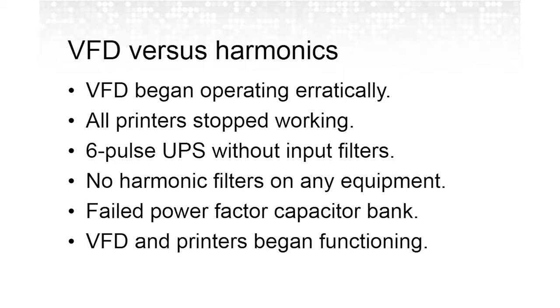Just as an example, in my office a few years ago, we had a VFD on a small machine that began operating erratically, and all of the printers in the whole building quit working. What we found was we had a 6-pulse UPS that had no input filters. It was an older uninterruptible power system, and it had no input filters at all, and none of the VFDs had any input filters. We traced the actual source of the harmonics that were creating the problem back to a failed power factor correction capacitor bank. We were able to get the capacitor bank back online, and the VFD and the printers began functioning normally again.